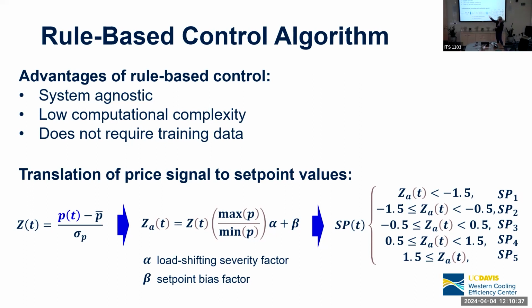And then we can add a set point bias factor if needed to skew the prices set points higher or lower. So that we take in the prices, run them through this, we get 5 different bins of set point signal for both the HVAC system and water heating system. And we apply this for each hour in a 24-hour period. So this is done once at midnight and it's giving you set points based on prices for the following day.